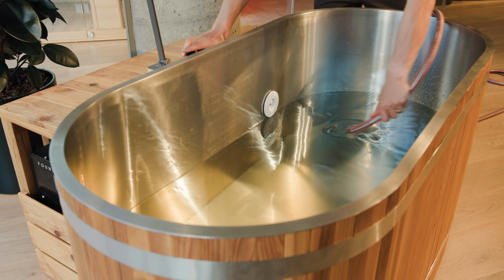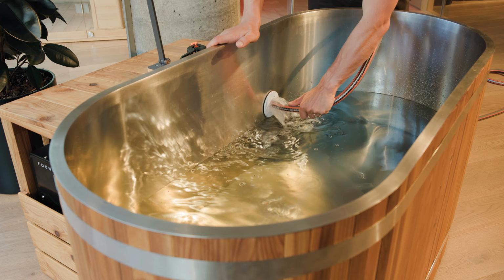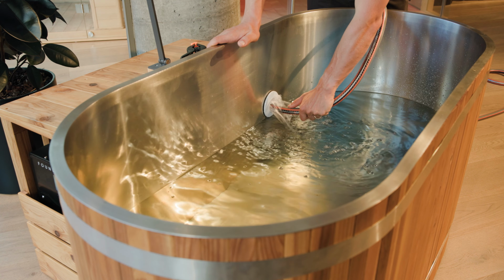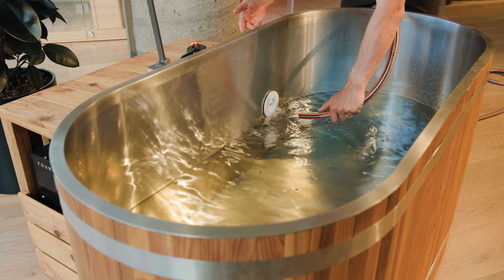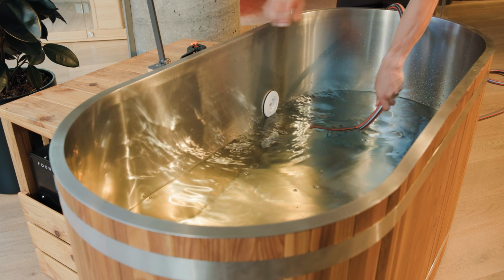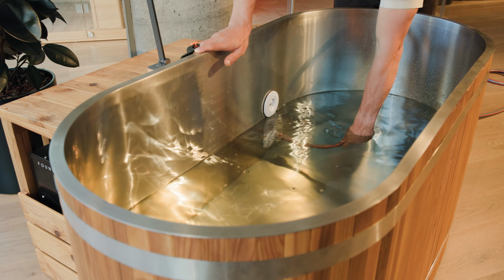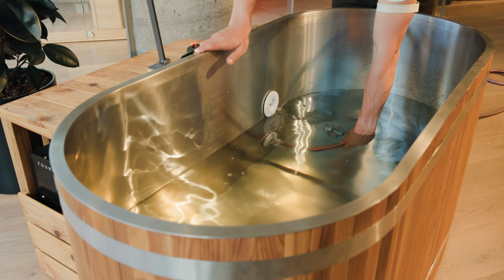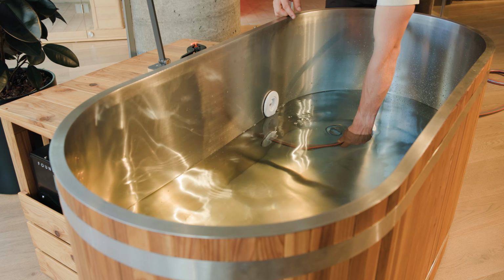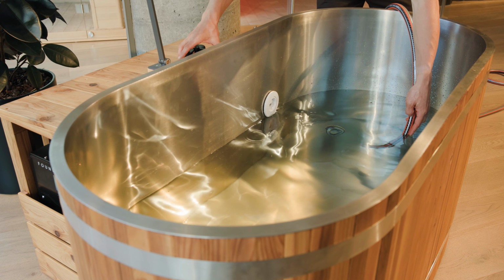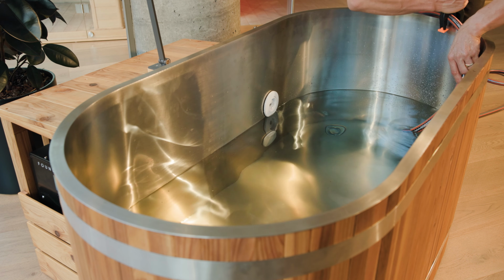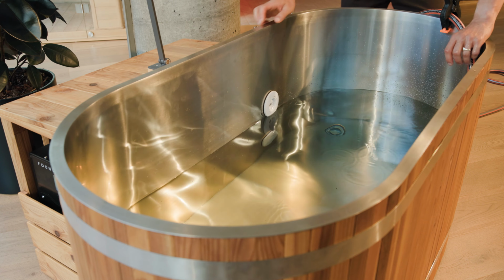The way to remedy that is to send the hose into the top inlet. That will fill the chiller with water from the top and help it prime. Sometimes we may also need to put some extra water in the bottom, which will also get water into the chiller and help clear out any airlocks. That way the chiller will start to run.